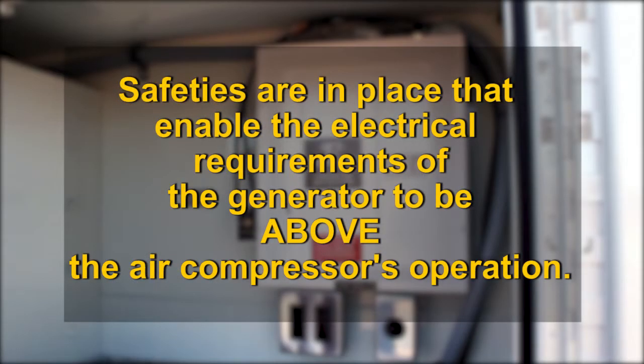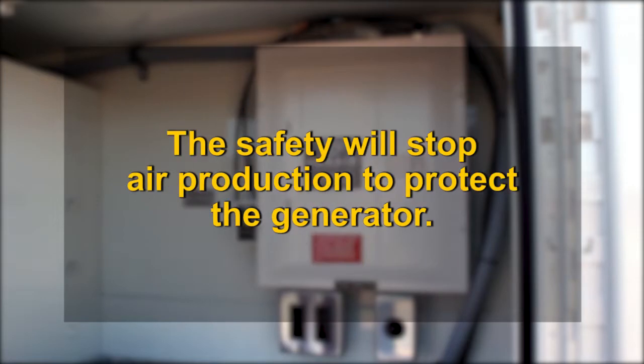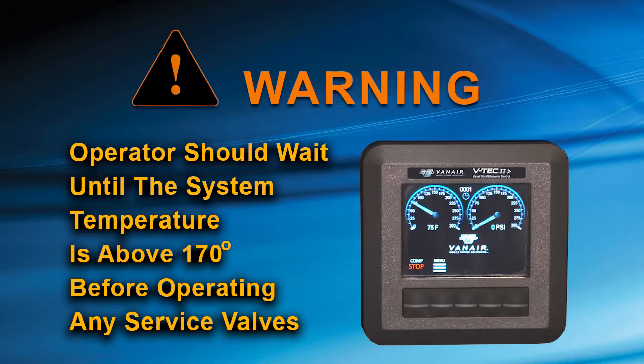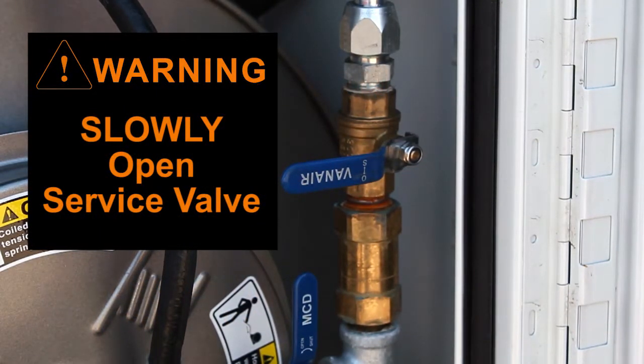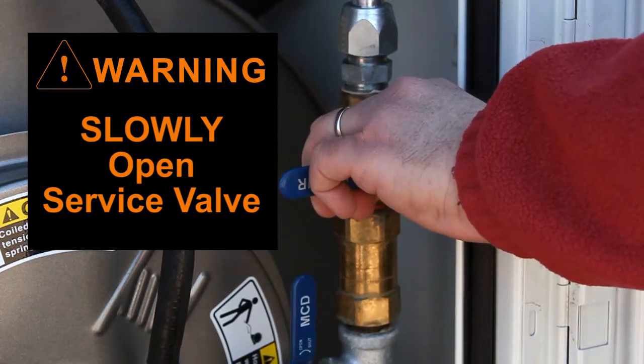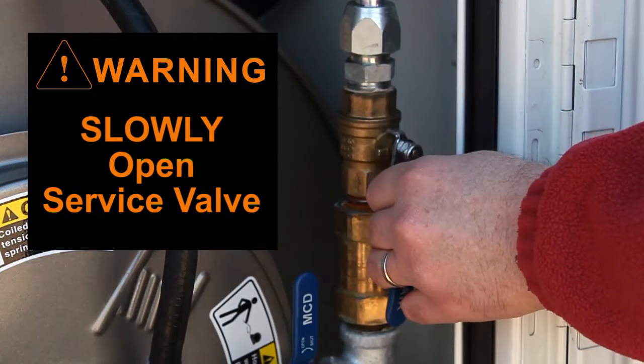Note that while you may operate both the air and electrical systems at the same time, there is a safety in place that puts the electrical requirements of the generator and its safety above the air compressor operation. The safety will stop air production to protect the generator. Warning: at this point, the operator should wait until the system temperature is above 170 degrees before operating any service valves. Look at your VTEC 2 display for this temperature indicator. Slowly open the service air valve. Quickly flipping the service valve open will cause a rapid discharge of air from the separator tank and may damage the separator element.